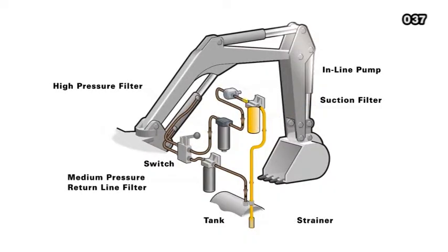From here, the oil, which has been filtered of potentially damaging particulate matter, goes through the inline pump. It is then filtered again in the high-pressure section of the circuit. This second filtration is to protect the expensive hydraulic components, the muscles of the system, from particulate and debris.